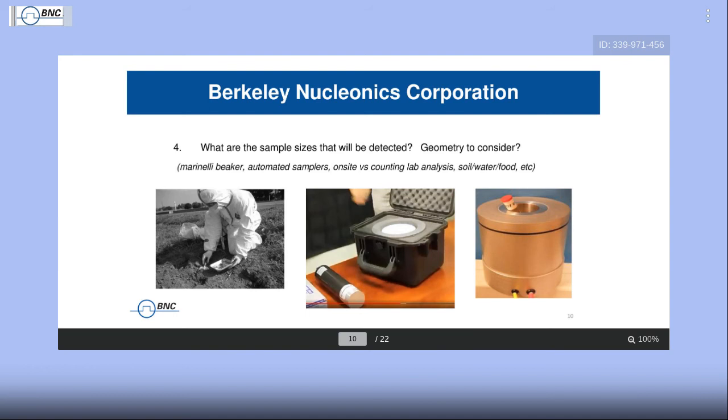Are you looking at very small activity over a very large area? Then you may have to scoop up large areas and sample them a little bit at a time, or use a very large detector. The 2x4x16 sodium iodide detector that David was showing a moment ago is quite commonly mounted portably on something like a golf cart or other vehicle to cover a fairly large area. Very helpful in remediation.